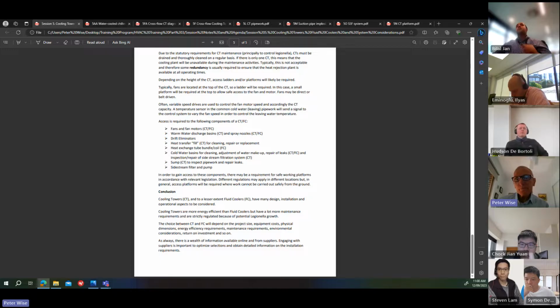Yes, that's one option for sure. You can, and normally you do that anyway with chillers. You have them running, they might run for a day or 2 days and then swap over to another one. If you're in part load situations, you want to keep the water circulating as much as you can. Is there any typical frequency in terms of how often you should rotate it? Different clients, different owners of the building will have different preferences, but if your chiller's running fairly constantly, you might change them over once every couple of days, perhaps once a week.